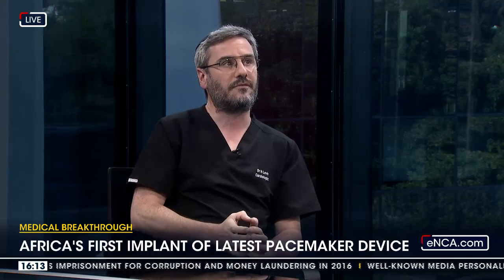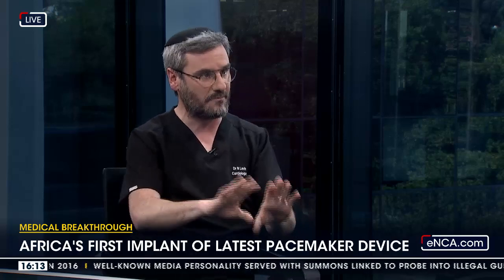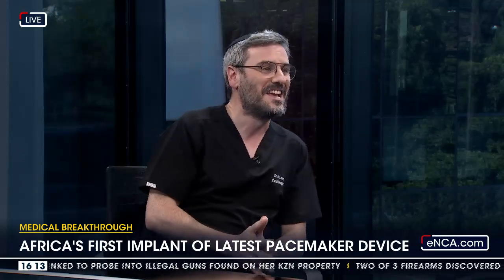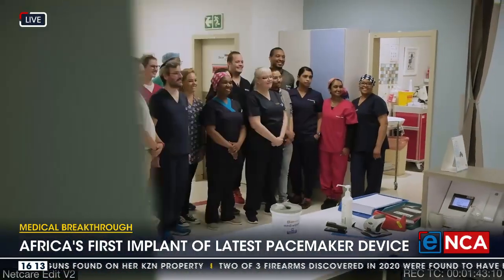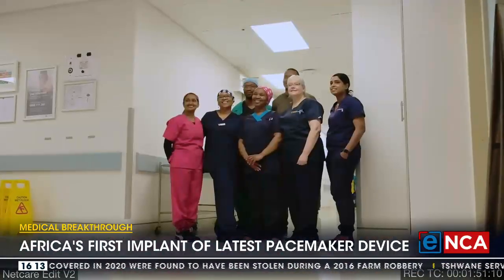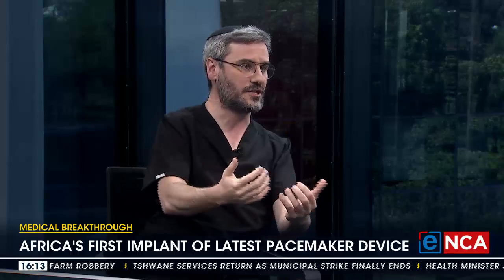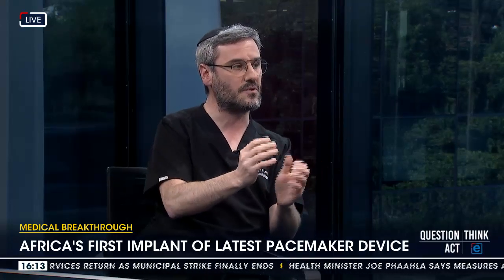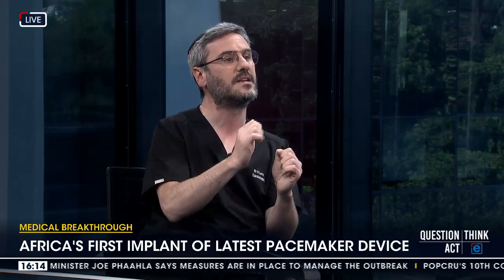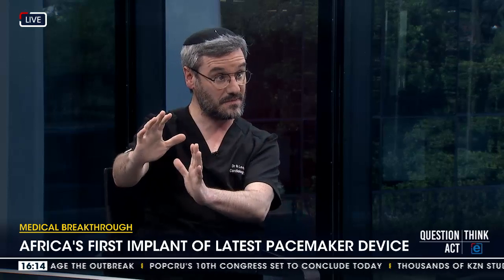This particular case was a less common occurrence — it's called cardio-inhibitory vasovagal syncope. We know people sometimes pass out and say they've fainted. Most of the time fainting is not due to this condition. In this particular case, normally when blood pressure drops the heart rate increases to compensate, but here there's an overwhelming drive to slow everything down. The heart rate drops in addition to the blood pressure and the patient passes out. This device can preempt when that's going to occur and act in advance to stop the symptoms.